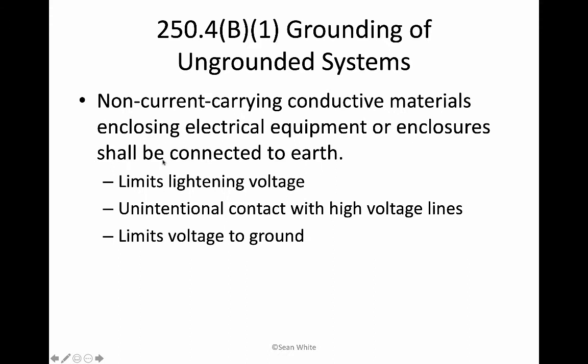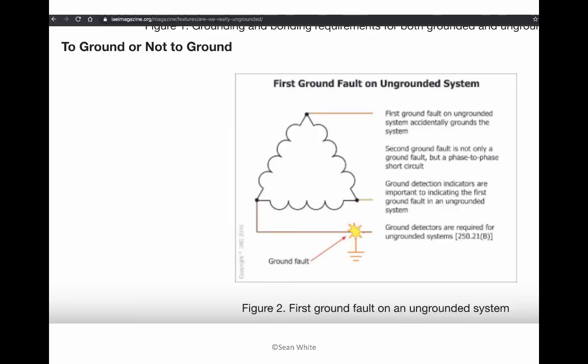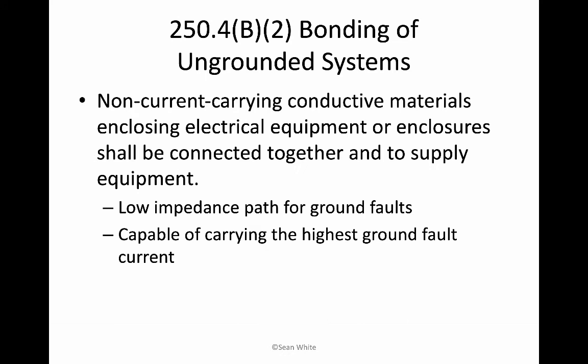And so some of the things that connecting to earth does for your ungrounded system: it limits lightning voltage, unintentional contact with high voltage lines, and limits voltage to ground. So you always ground your system. You always make sure that your things are bonded and grounded. And so let's look at our bonding part.